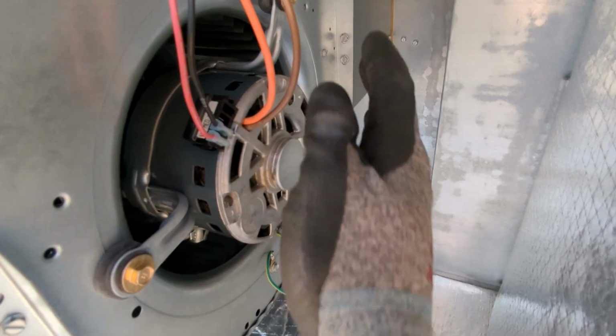I realized what I did later on. I got them confused. To take out the condenser fan motor, you've got to remove the wires from the control board. For a blower motor, the wires usually go in at the motor itself. So when you're changing a condenser fan motor, you replace the wires at the control board, but for a blower motor, you replace them at the actual motor. Anyway, I got all crazy and went in there trying to take out the wires.